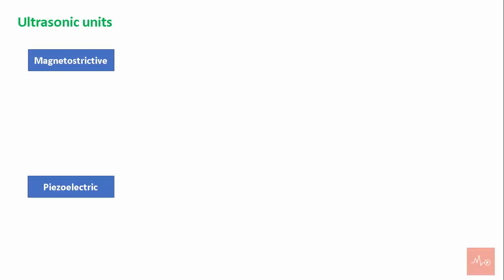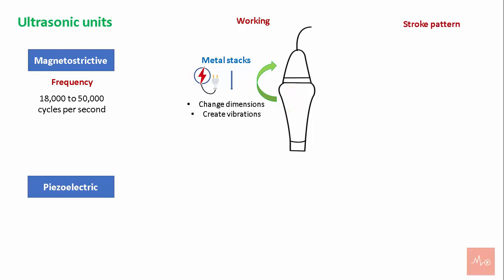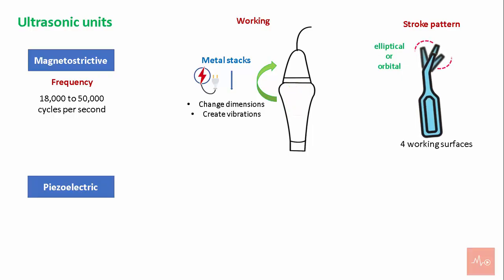Ultrasonic devices are of two types: magnetostrictive and piezoelectric. Magnetostrictive units work at a frequency of 18,000 to 50,000 cycles per second. The magnetostrictive unit consists of metal stacks that change dimensions when electric energy is applied. The vibrations from the metal stacks travel to a connected body, causing vibration of the working tip. The tips move in an elliptical or orbital stroke pattern, giving four working surfaces.